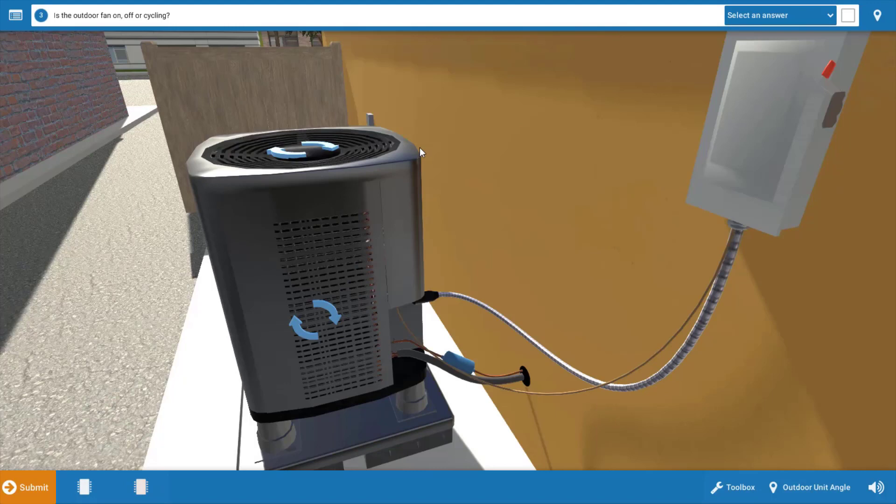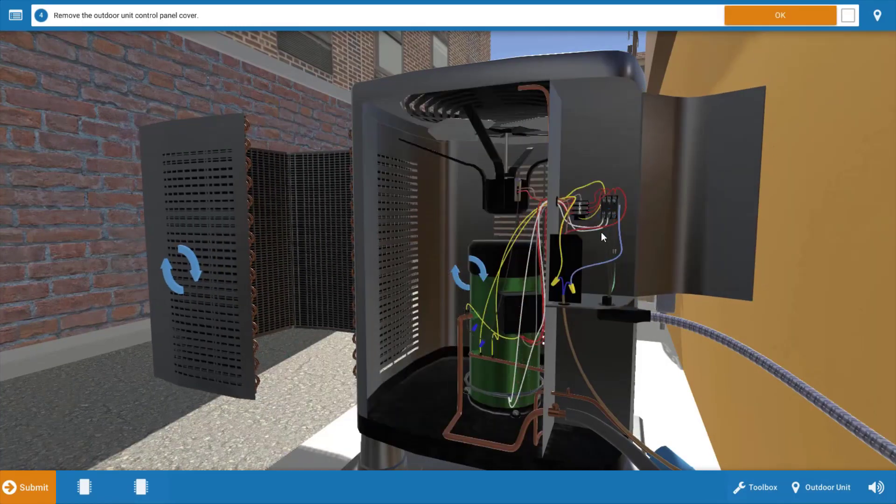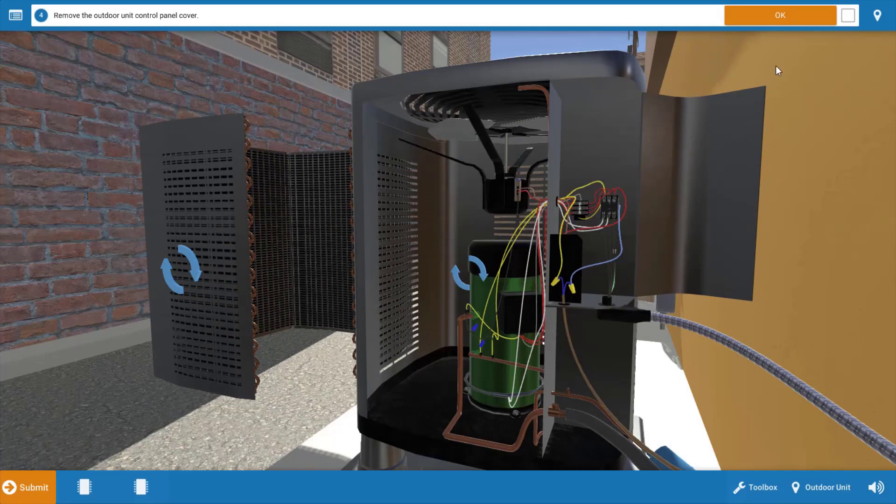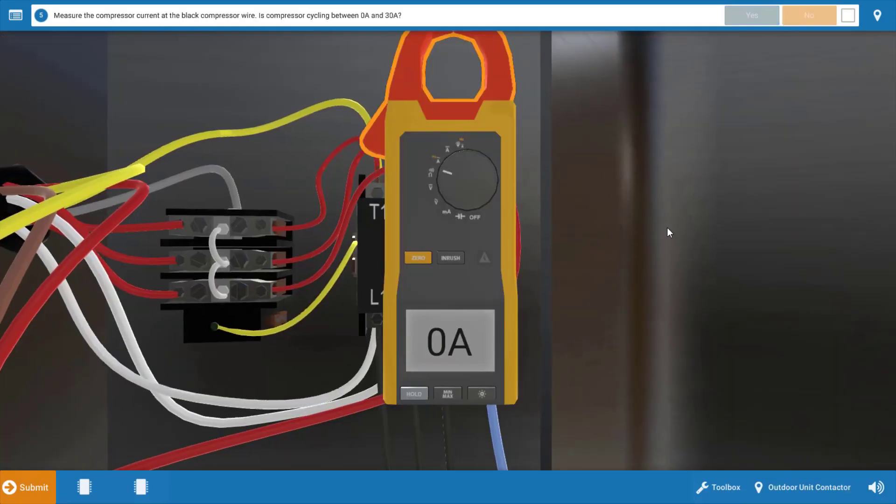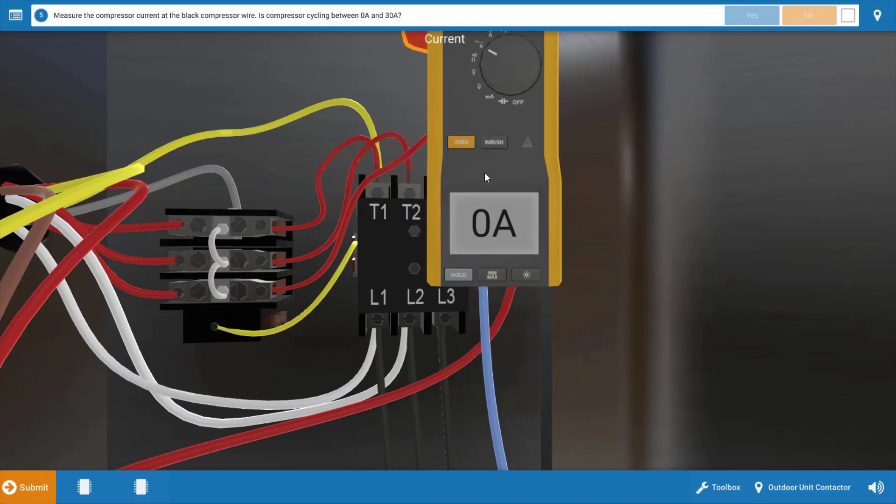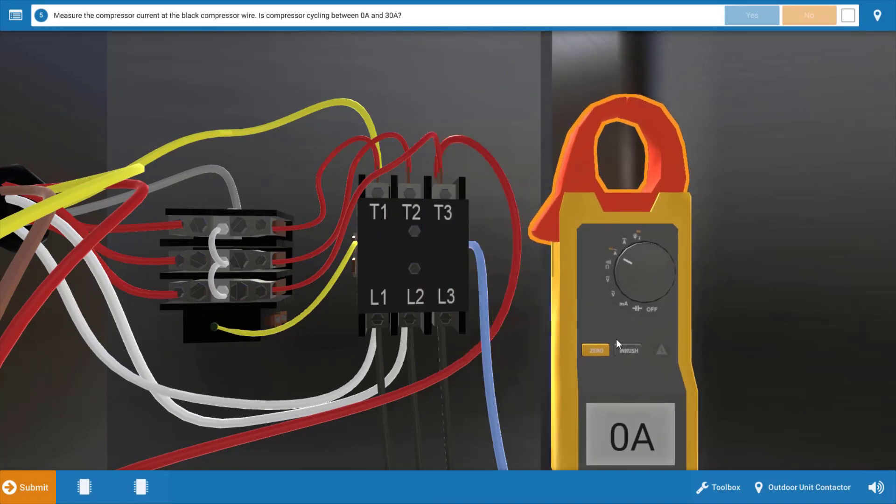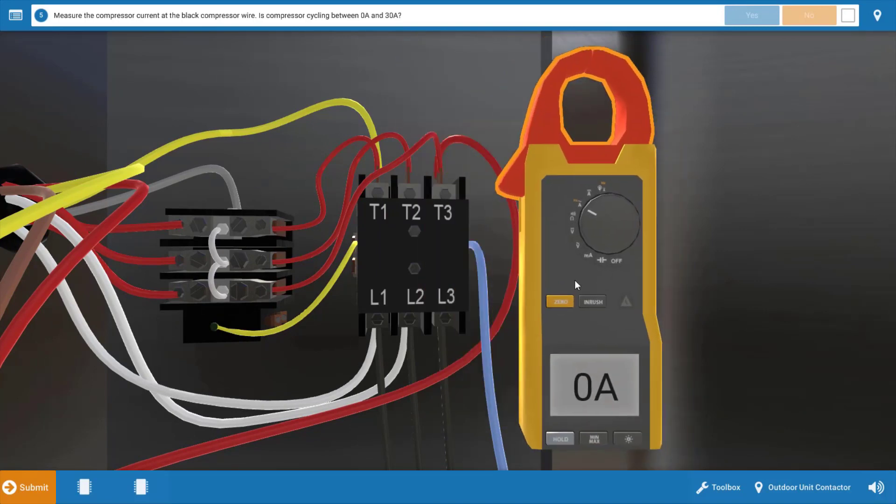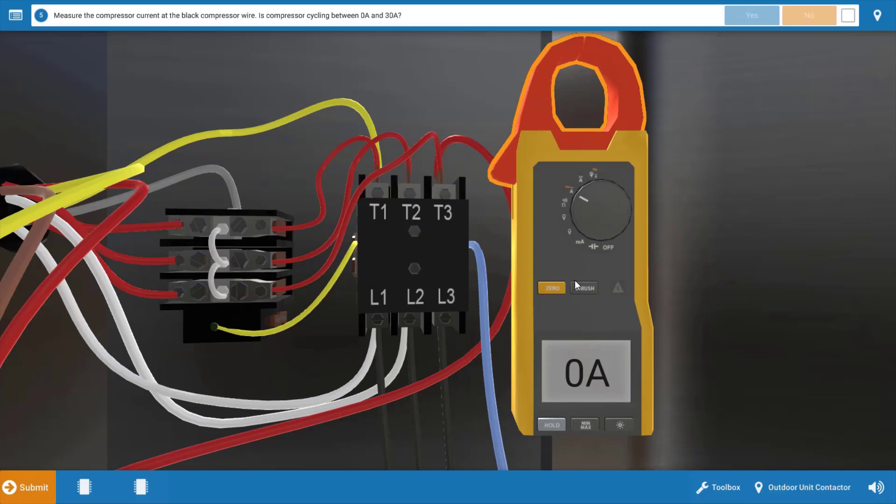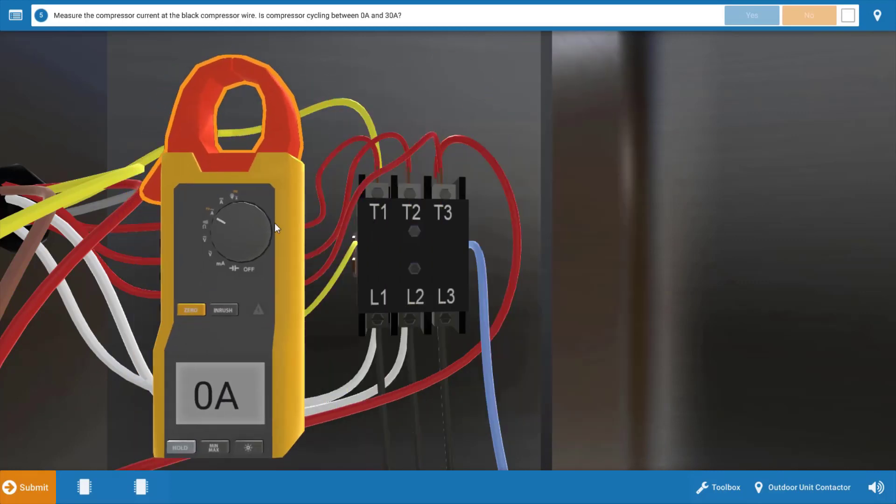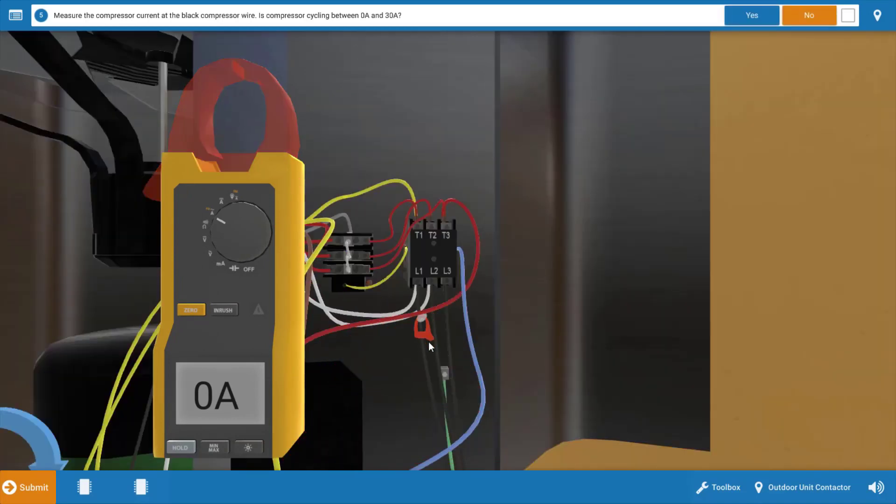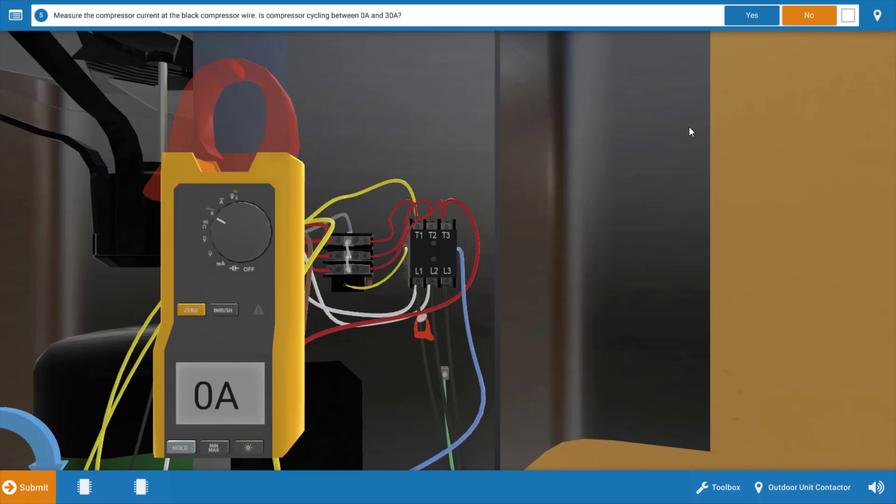Now, once you've clicked on the procedure guide that the fan motor is off and that the compressor is off, we're going to remove the control panel. Okay, once we've done this, click OK in the procedure guide. And we're going to just verify that the compressor is not cycling on a safety switch. So basically take your amp meter and place it at one of the leads going to the compressor. Now, you can do this by simply clipping the jaws around this black wire right here that leads to the compressor. And we can see we have zero amps here, and it doesn't appear to be cycling on and off. We've got a straight zero amps, which verifies that the compressor's not coming on at all, along with the condenser fan.